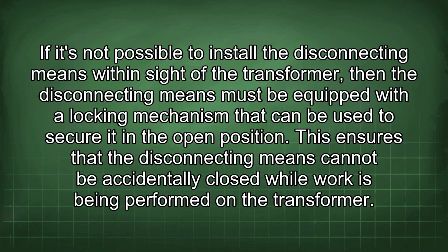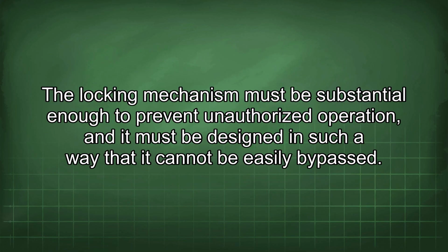If it's not possible to install the disconnecting means within sight of the transformer, then the disconnecting means must be equipped with a locking mechanism that can be used to secure it in the open position. This ensures that the disconnecting means cannot be accidentally closed while work is being performed on the transformer. The locking mechanism must be substantial enough to prevent unauthorized operation, and it must be designed in such a way that it cannot be easily bypassed.